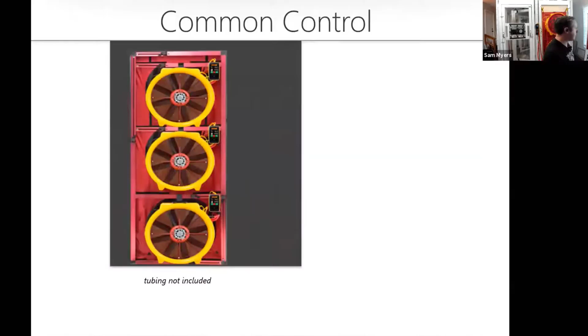What this means is called a master-slave relationship. This gauge here on top is the dominant gauge, telling the rest of the gauges or the rest of the fans what to do. This is unique to Retrotec fans, so this is where the 2 brands really differ.